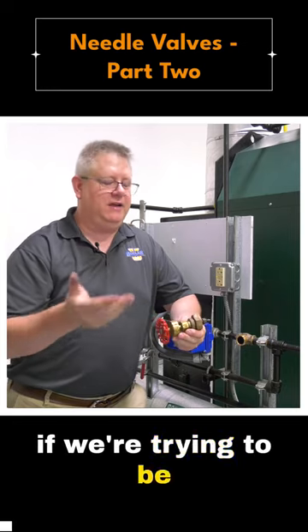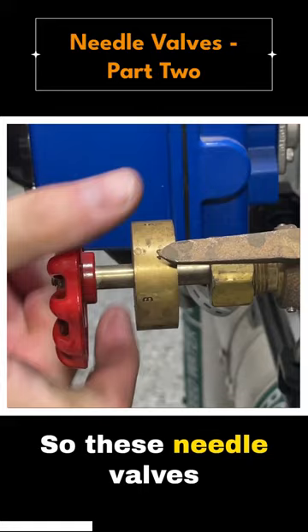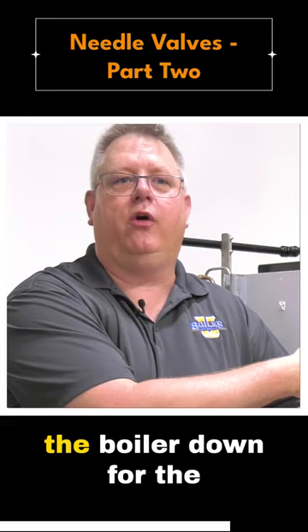Now if we're trying to be particular, one other thing that we'll often do on surface blowdown is note what our valve position is. These needle valves are actually equipped with a graduated scale to show the proportion that it's open. So if we finally get this set exactly where we want to control our conductivity but we're going to shut the boiler down for the weekend, we can close this and then reopen it to the same spot it was on Monday with pretty good reliability.